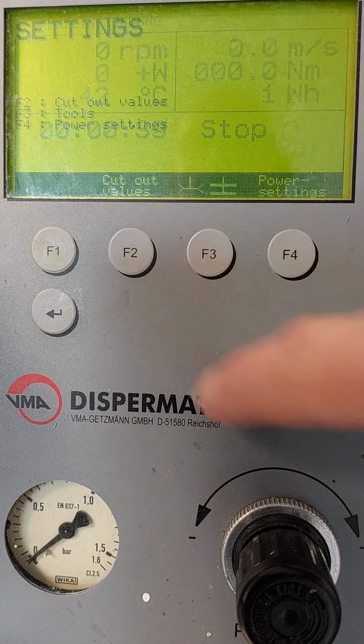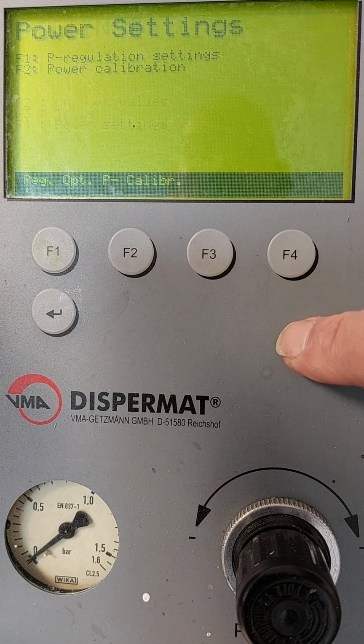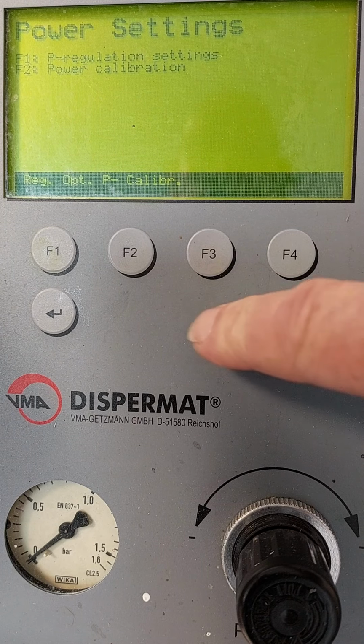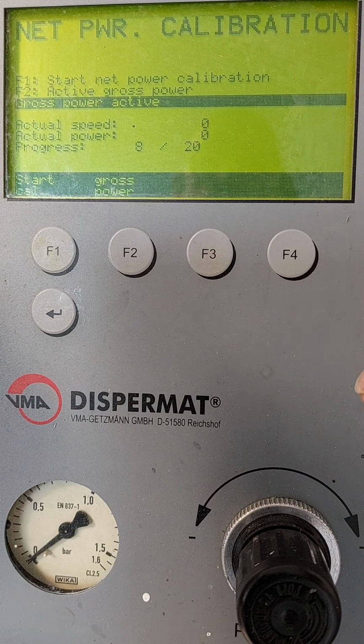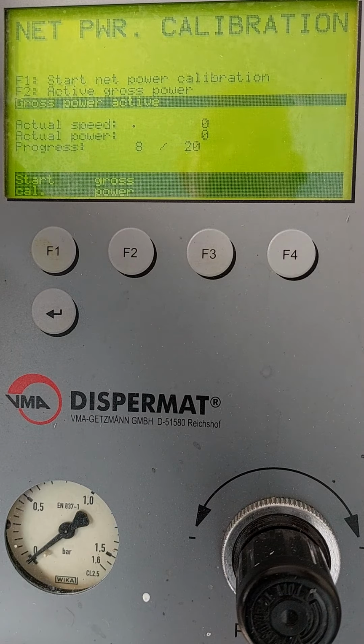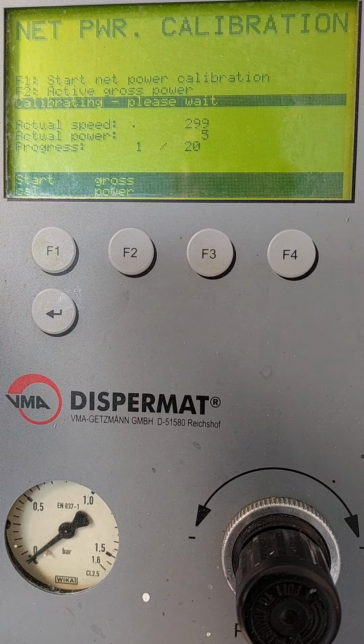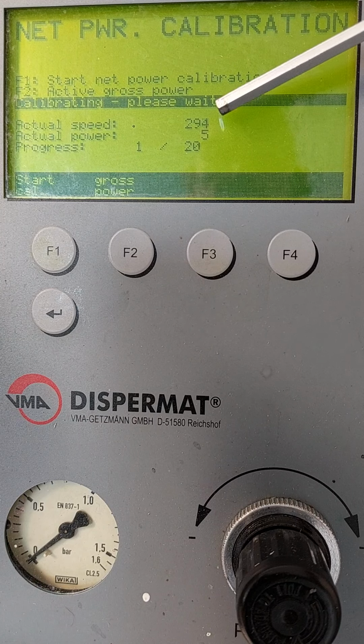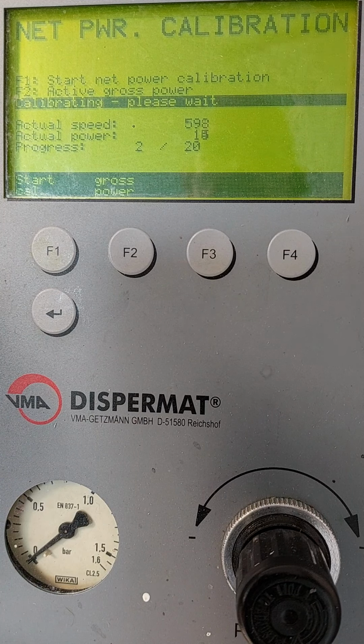If we press F1 for settings and go to F4 for power settings, we can run F2, which is a power calibration. The screen showing us that gross power is active, and if we start calibration, the mill will start to run. It's doing 300 RPM at the moment. It will ramp up through the speed and we'll measure the actual power and we'll subtract that so that we get a net power. So when we set the mill up, we will just be looking at the power that's going into the product.